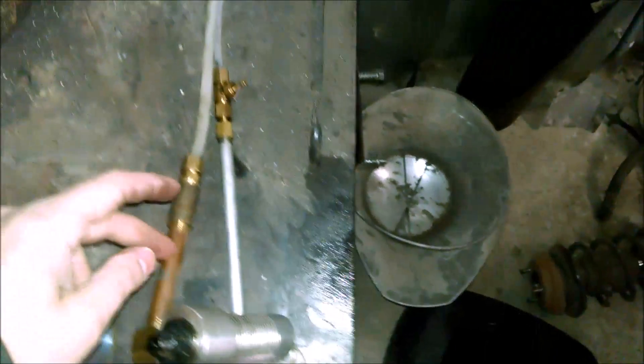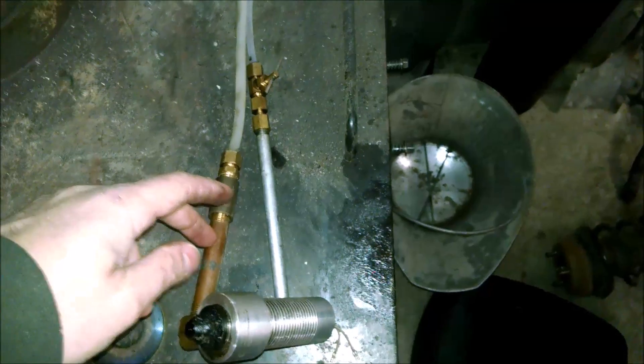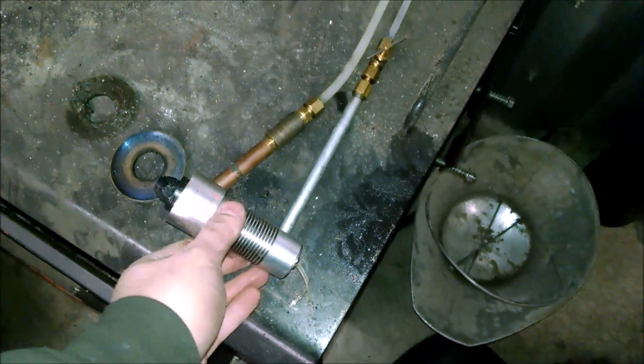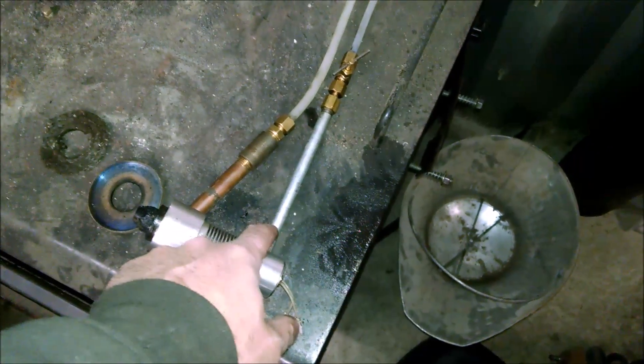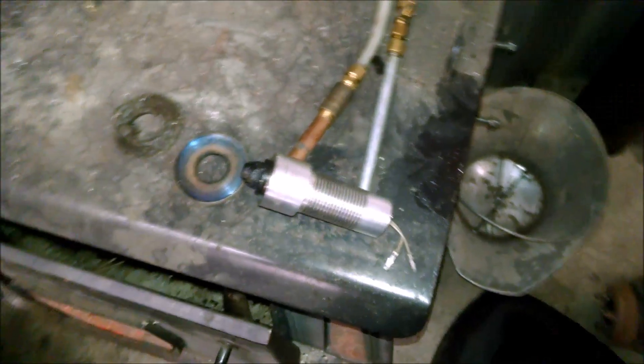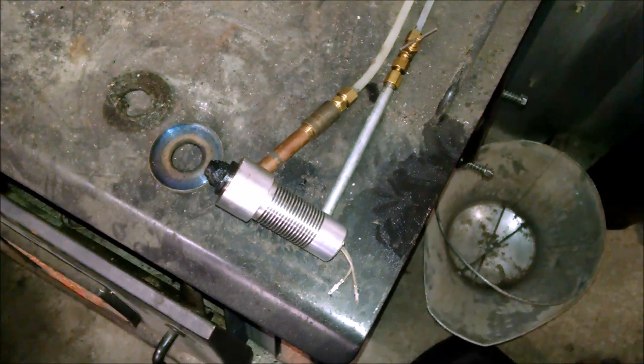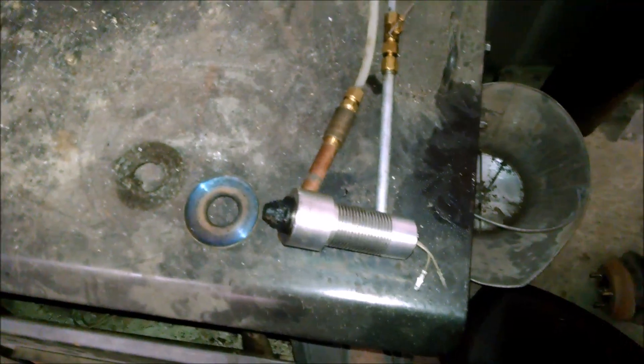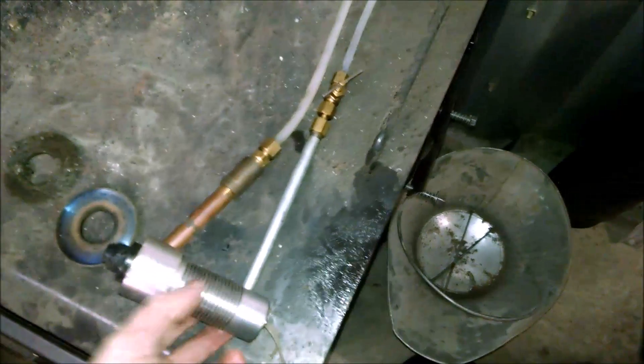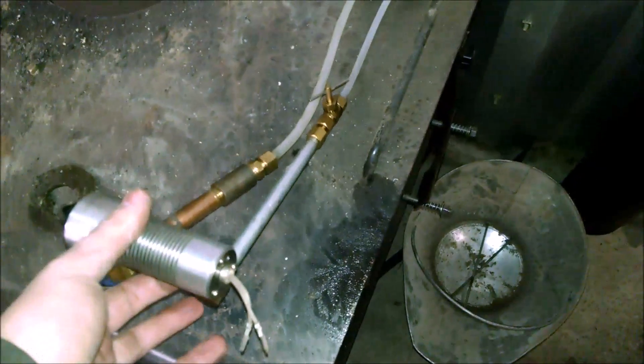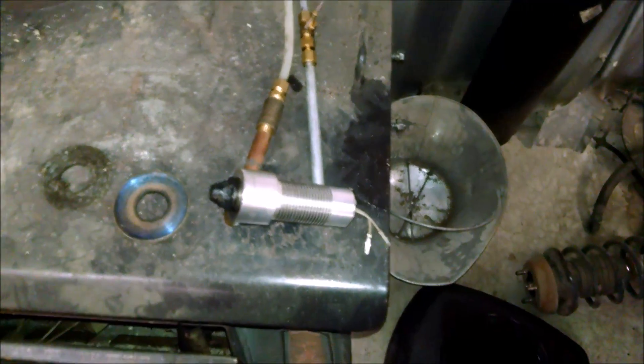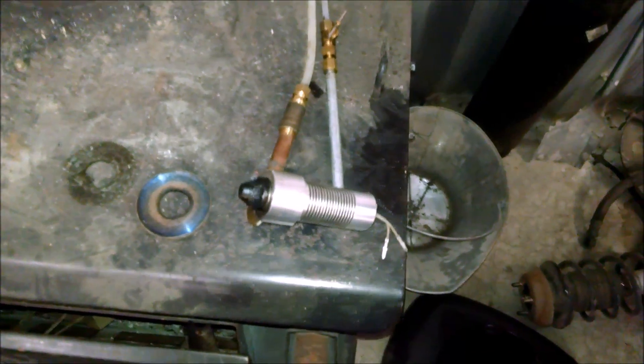What we've got is an air supply line, it only runs about 12 psi, and then a waste oil feed. These are actually made for heating oil, so they actually draw a vacuum on this line. The problem is heating oil is quite a bit thinner, lower viscosity than waste oil. If waste oil you have two options: you can either preheat the oil and place it in a holding tank about three to four inches below the level of the nozzle, or the other option is to pressurize oil to it, which is what I've done.